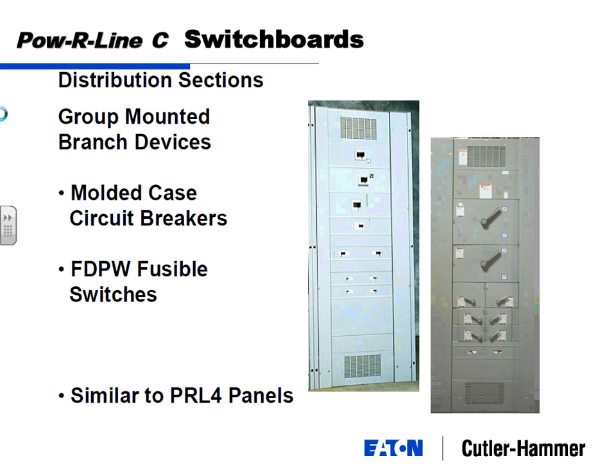Distribution sections of switchboards are really the same as the Powerline 4 panelboards. It does have the capability to go to a lot higher amperage, but the design and the construction is the same. Breakers mounted upon breakers. They're called group mounted. Group mounted is basically just stacked on top of the other. When I talked about if one fails, you're possibly going to blow down on the next one.